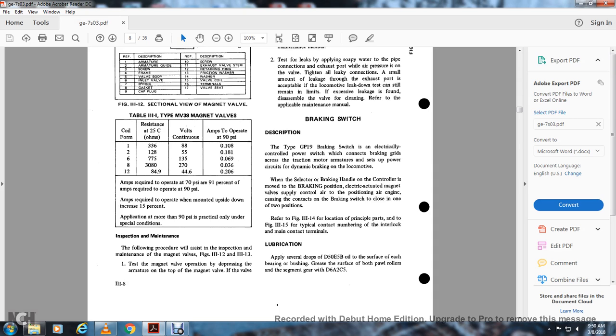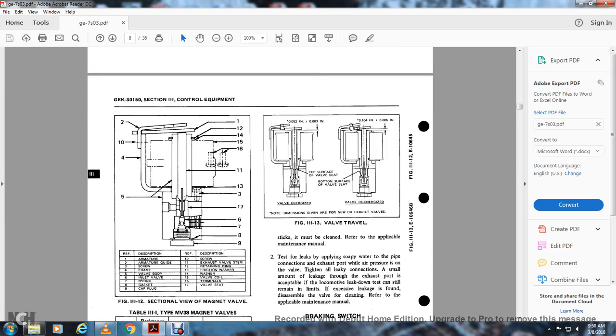Inspection maintenance. The following procedure will assist the inspection maintenance of the magnet valve, Figure 313. Test the magnet valve operation by depressing the armature at the top of the magnet. If the valve sticks, it must be cleaned; refer to the applicable maintenance manual.